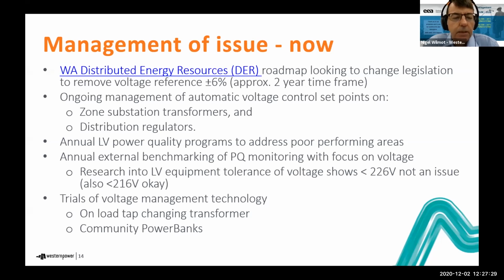The other thing that we're doing is we've dropped the voltage. No longer is our starting point on the LV network at 250 volts. We now adopt between 5 and 10 volts lower. And so our starting voltage on networks is starting to be in the range of 240 to 245 volts. And this was being done by changing automatic voltage control points on zone substation transformers, and also on our downstream distribution regulators. We also, because we then have a challenge of undervoltage, will continue to do power quality programs to address poor performing areas.